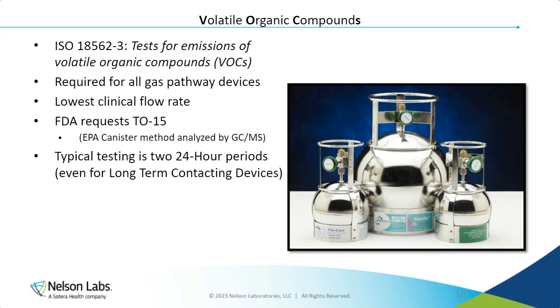device. This flow rate, however, differs from particulate testing, as we need to look at the lowest clinically relevant flow rate. If, for example, the lowest flow rate of the device is 0.5 liters per minute, it may not be a bad idea to test at 0.1 liters per minute, just as long as it's below that 0.5.